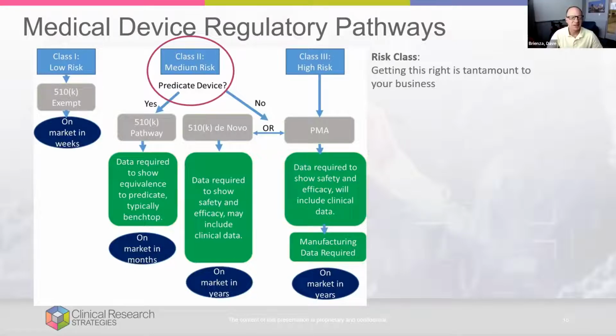Julie, a quick question on the predicate device. Is the predicate device approval based on the function or the form? So in other words, for example, we work in wheelchair seat cushions. And there is a predicate wheelchair seat cushion out there and it's made of foam. And we invent one that's made up of some elaborate mechanical structure. But I know that people use the foam cushion as the predicate. So I'm wondering, is that always the case? Is it based on what it does or what it is?